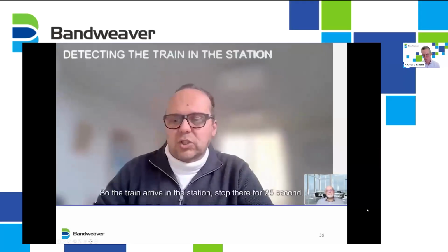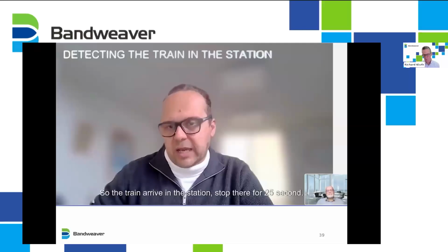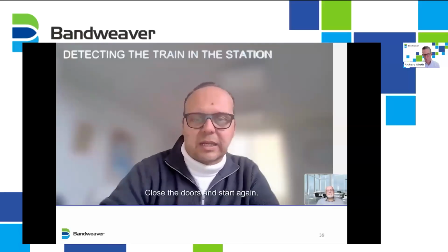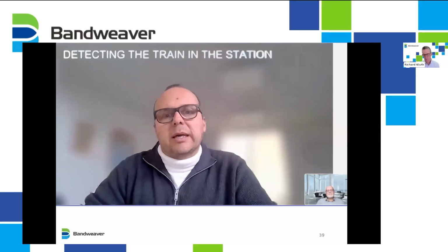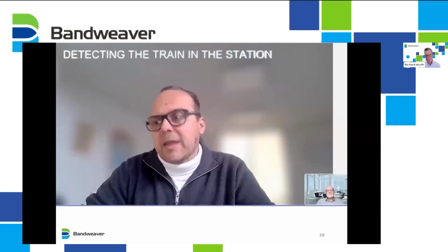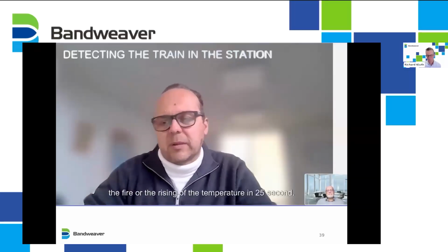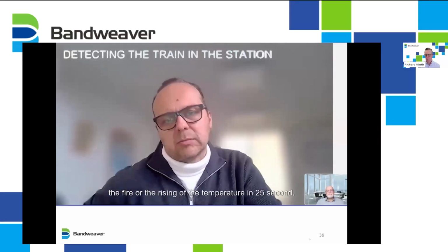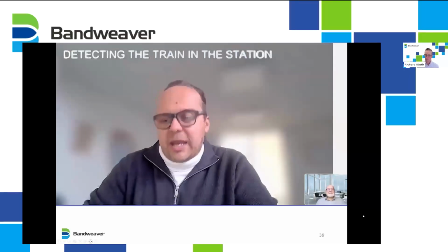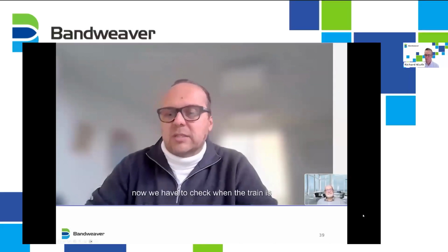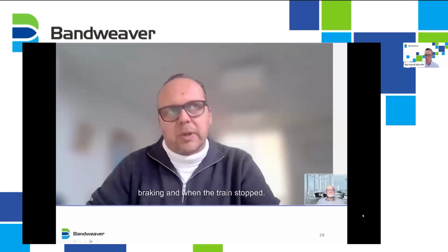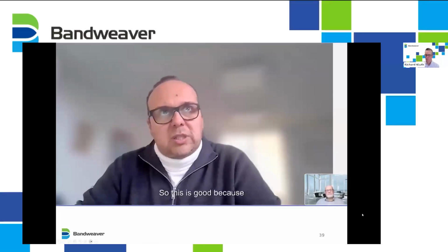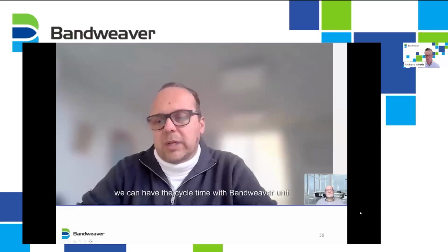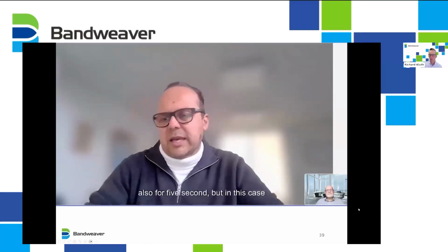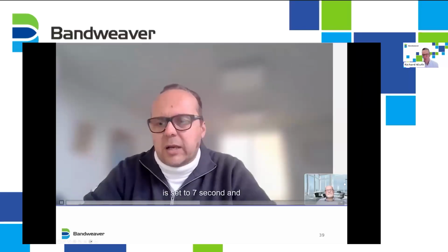So the train arrives in the station, stops there for 25 seconds, closes the doors and starts again. So it's important to check the fire or the rising of the temperature in 25 seconds. We have to check when the train is braking and when the train is in stop. So this is good because we can have a cycle time with the Bandweaver unit of even 5 seconds, but in this case it's set to 7 seconds.